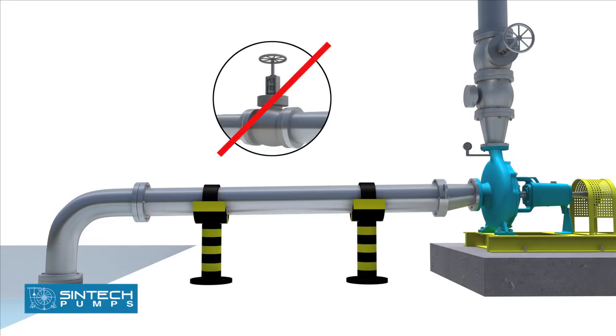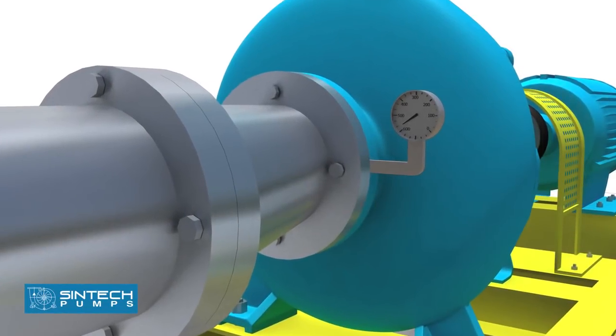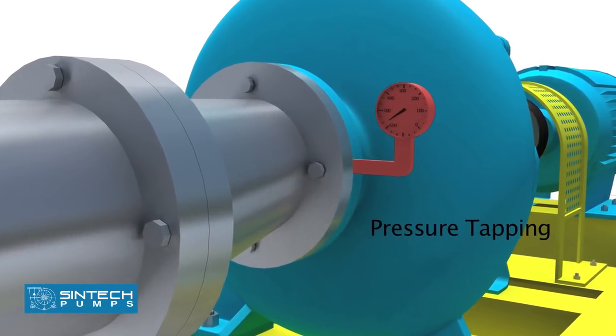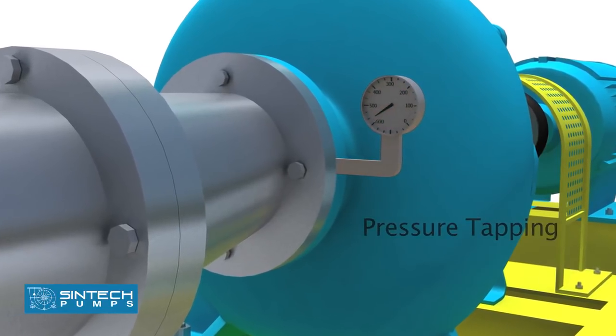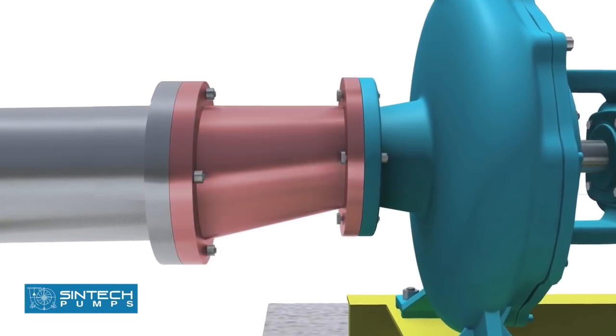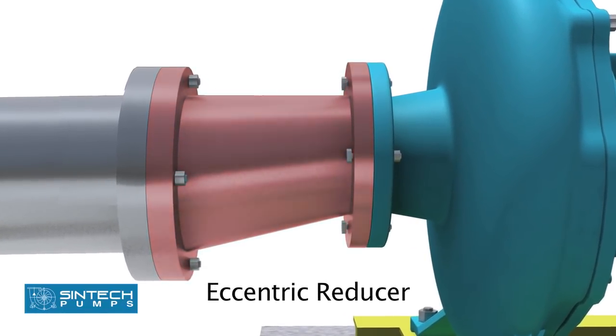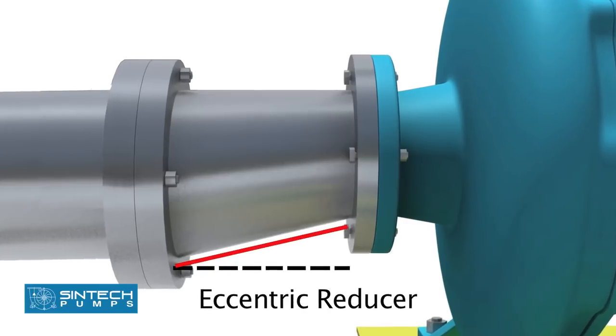No isolation valve is recommended. There should be a tapping provided for installing a vacuum gauge in the suction line. The reducer joining the straight length of the pipe in the pump line should be an eccentric reducer with the inclined side of the reducer as the bottom side.